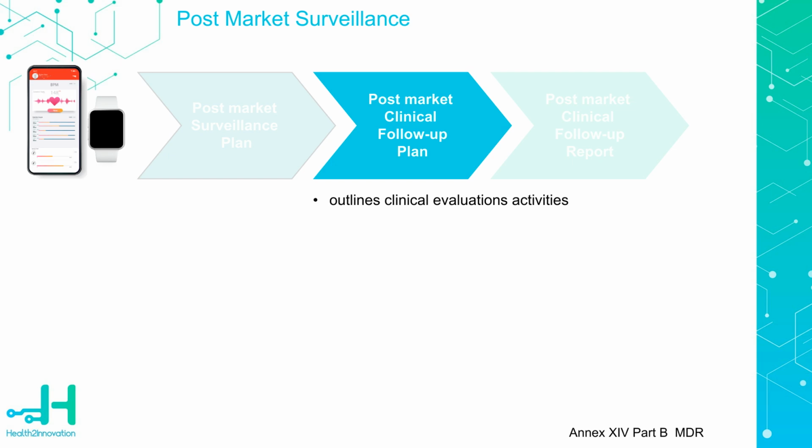Rationales against a PMCF plan could be made for certain low-risk devices where the already planned post-market surveillance is deemed adequate, as well as devices based on well-established technology with a long history of safe use, or for devices where there is already a significant amount of clinical data that demonstrates the device's safety.